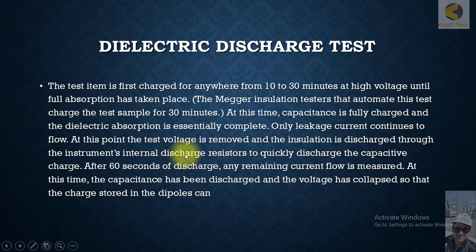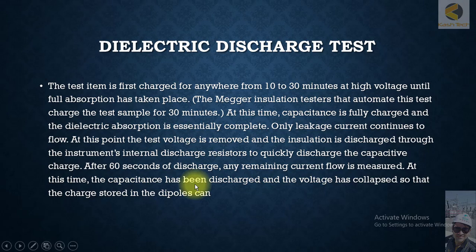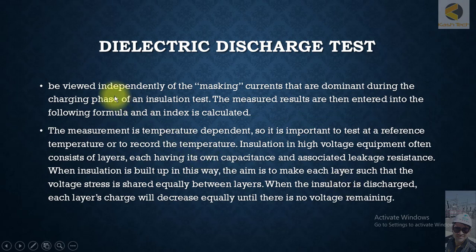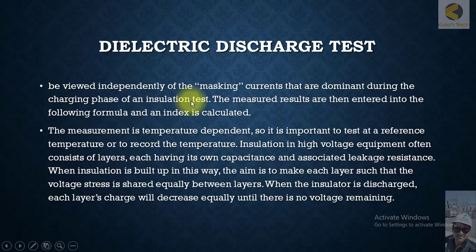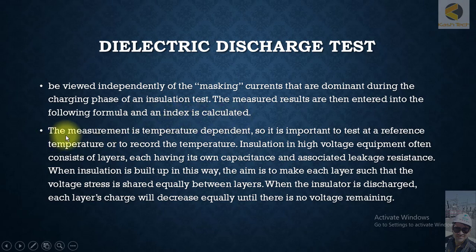At this point the test voltage is removed and the insulation discharges through the instrument's internal discharge resistors, which quickly discharge the capacitive charge. After 60 seconds, any remaining current flow is measured. At this time the capacitive charge has been discharged and the voltage has collapsed, so that the charge stored in the dipoles can be viewed independently of the masking currents that are dominant during the charging process of an insulation test. The measured results are then entered into a formula and an index is calculated.